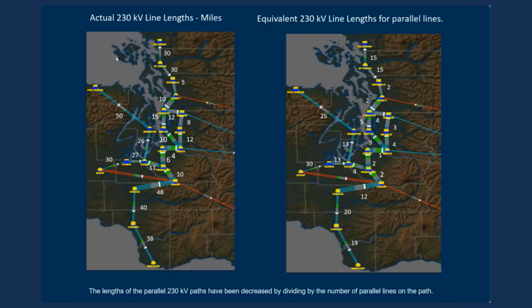The first step in the transformation is to take all the parallel 230 kV lines and reduce the length of the path by combining the lines in parallel. So the effective path length between Chehalis and Auburn, which has 4 lines in parallel and a length of 48, is really equivalent to a single line with 12 miles. So where we have 2 lines, we're reducing it by a factor of 2, 4 lines by a factor of 4, and 3 lines, it's by a factor of 3. And we're rounding the miles off to the nearest integer. So that's a fairly straightforward transformation.